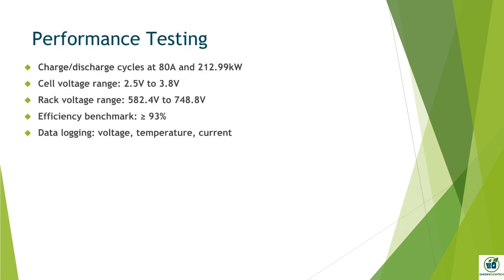Performance testing simulates real-world load conditions. The system is charged and discharged at 80A and 212.99 kilowatts. Cell voltage must remain between 2.5 V and 3.8 V, and rack voltage between 582.4 V and 748.8 V. We monitor temperature, voltage imbalance, and efficiency, targeting a minimum of 93%. This phase confirms that the system can handle operational stress without compromising safety.